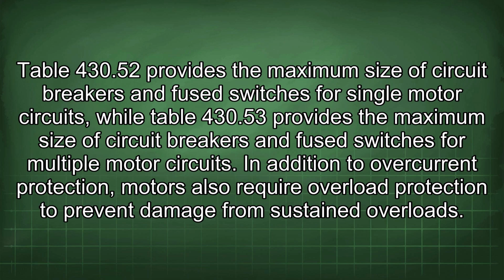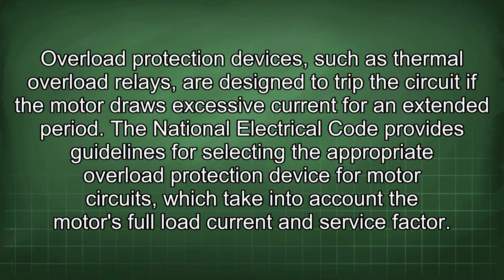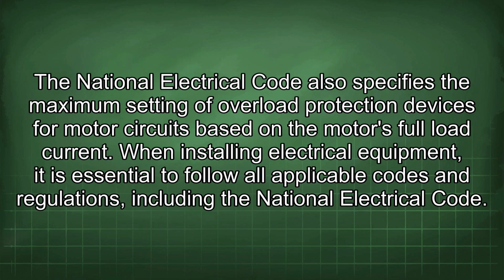In addition to overcurrent protection, motors also require overload protection to prevent damage from sustained overloads. Overload protection devices, such as thermal overload relays, are designed to trip the circuit if the motor draws excessive current for an extended period. The National Electrical Code provides guidelines for selecting the appropriate overload protection device for motor circuits, which take into account the motor's full load current and service factor. The National Electrical Code also specifies the maximum setting of overload protection devices for motor circuits based on the motor's full load current.